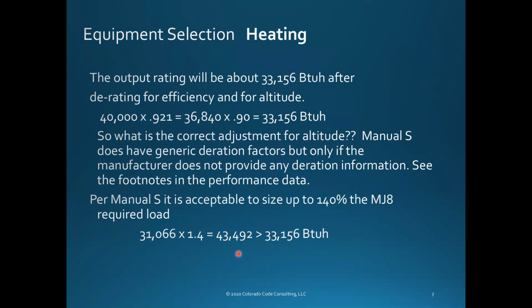Oversizing on the heating equipment is not as large an energy penalty as it relates to air conditioning. Air conditioning, it's a horrible oversizing thing, right? But there's reasons we'll go over when we get to air conditioning. It might be a little bit higher than the acceptable oversizing.